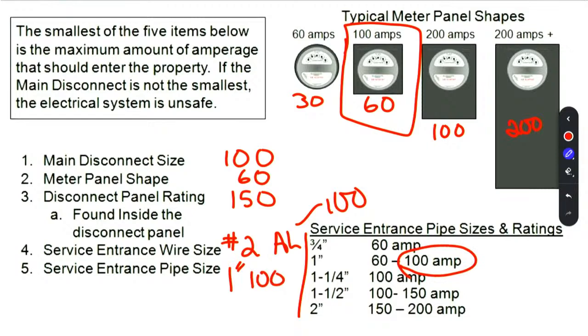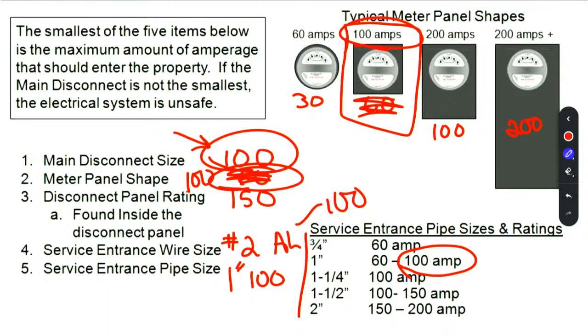So we look for the smallest number of the 5. The smallest number is going to be 60, and that 60 amps is going to be my amperage. However, because the disconnect allows up to 100 amps, we'd be allowing 100 amps to flow through something that's only designed to carry 60 amps. That's not safe. Now if we use 100 amps here instead, then 100 is my smallest number, 100 is also my main disconnect, 100 is my amperage, and it's safe. I hope that makes sense.